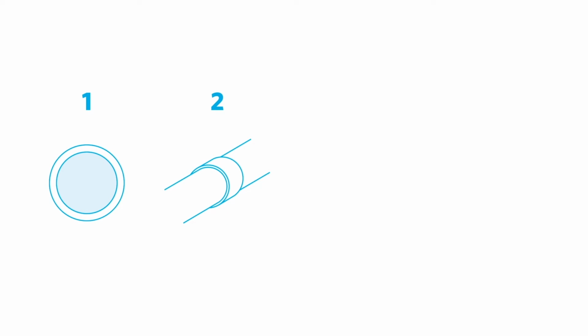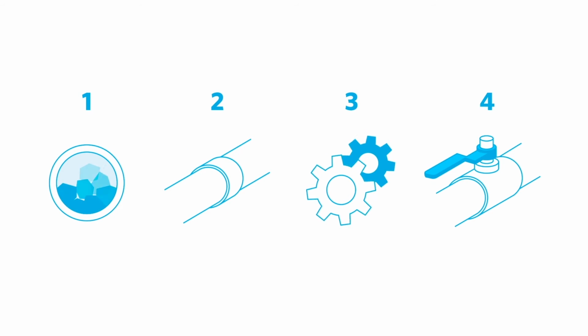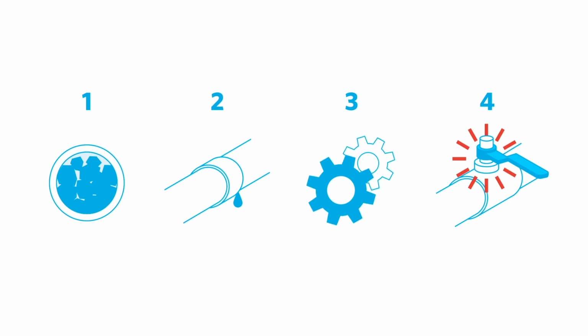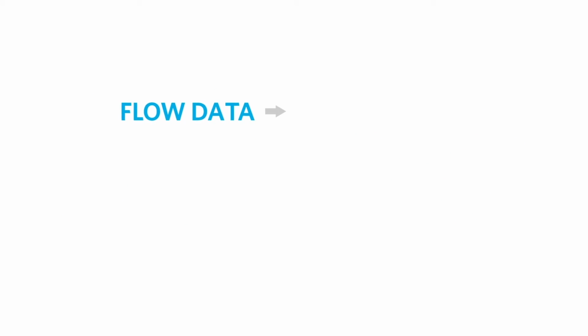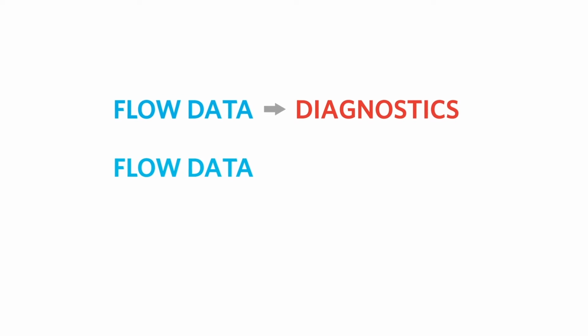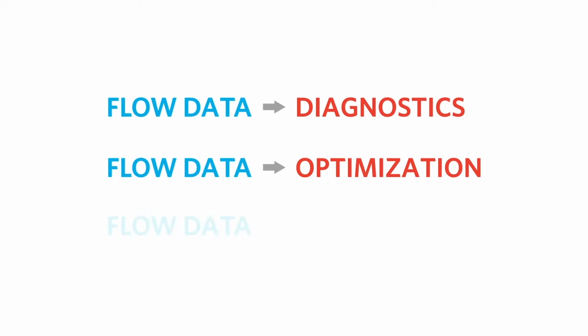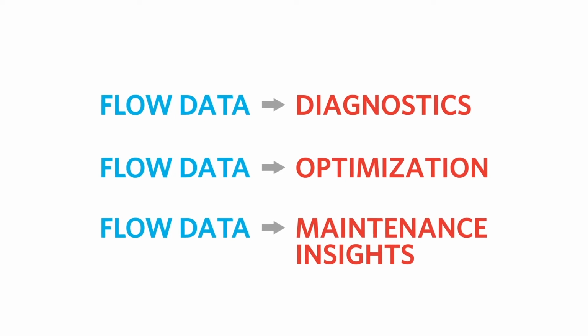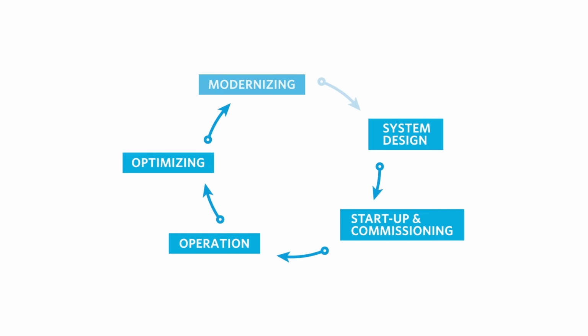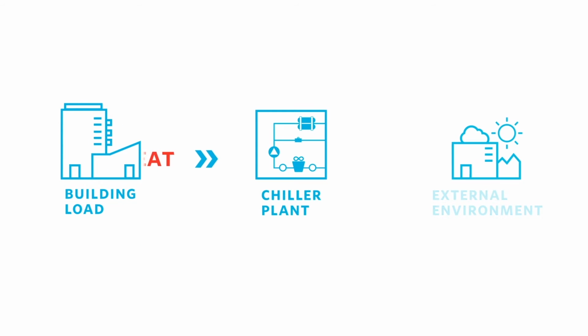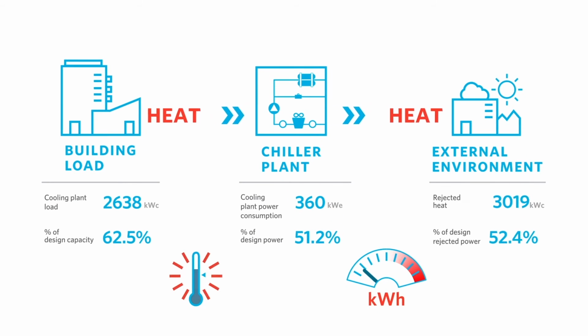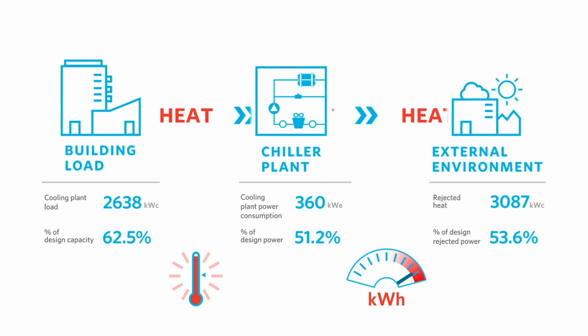In the circuit, changes in flow rate that can't be explained by demand may indicate clogging, leakage, changes in settings, or valve malfunction. Flow data gives us new abilities for diagnostics. It provides clues for new optimization approaches. It gives us more data for performance commitments and condition-based maintenance. Flow data can provide valuable insights at every stage of your building's life cycle and can have a direct impact on occupant comfort, energy savings, and equipment availability. Accurate flow data from both sides of a heat transfer device enables a clear assessment of an HVAC system, long before restrictions in flow cause problems in performance and occupant comfort.